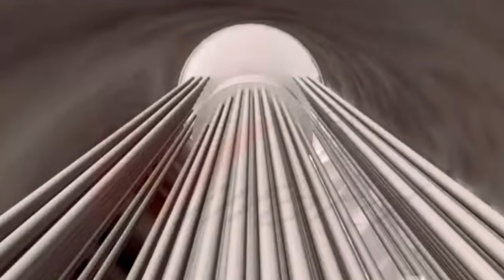The poor coal was bought from developing mines at a very cheap price, cutting costs. To cut costs further, coal washing was not done. The mills struggled to grind the coal, which reduced coal flow to boilers and lowered the output. As a result of the poor coal, slag began accumulating in boiler tubes, which caused the tubes to fail. This also led to difficulty in meeting environmental limits.